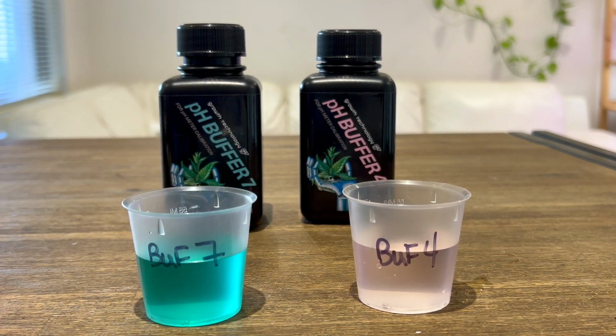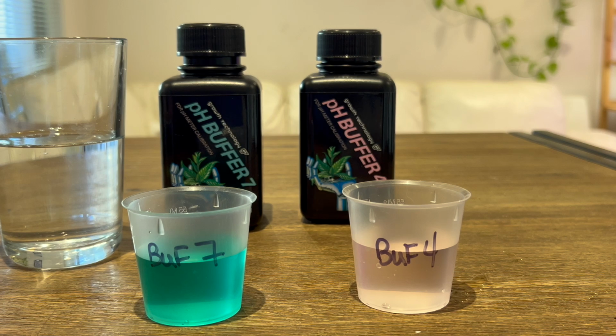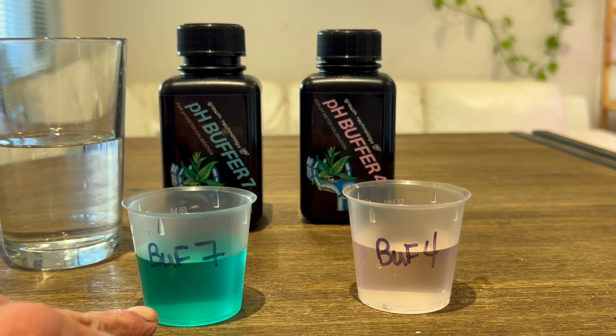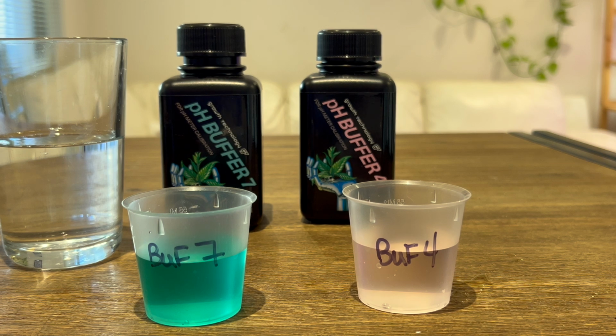So what else do we need here? Well, we need something to rinse in between our calibrations. So I'm going to go grab a little bit of RO water, and I'll be right back. So now we've got our RO water, and we're going to use that to clean this in between things. Now, the important thing to know is that when you start your calibration process, you want to start with neutral first. So your buff 7. So 7 is considered pH neutral, and always start with pH neutral or closest to pH neutral first.